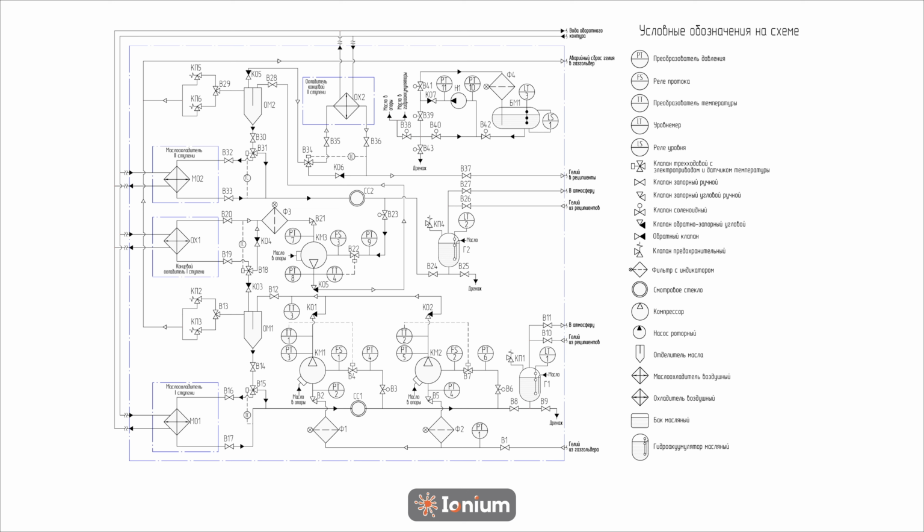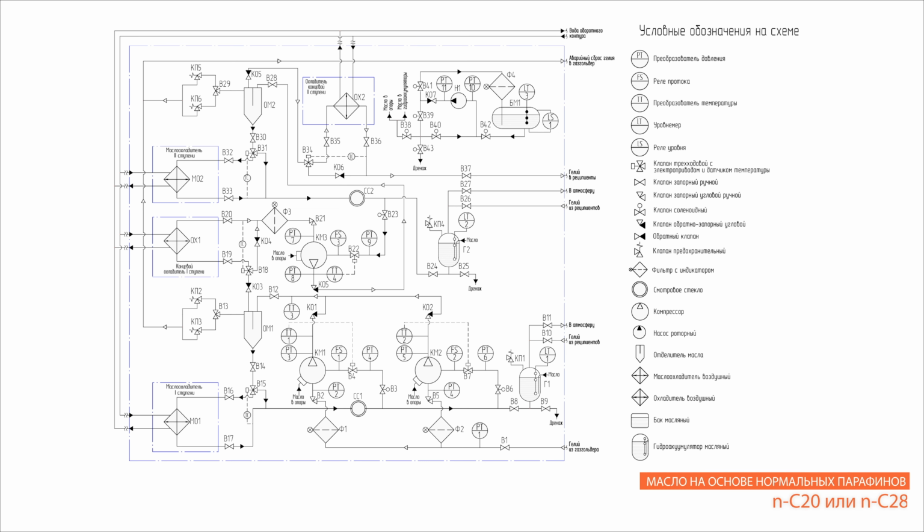To seal gaps between screws and casings, as well as to internally cool helium, an oil based on standard paraffins is used: n-C20 and n-C28, which include antioxidants and stabilizers like phenol. The machine is approved for use with a specified oil if the helium temperature at intake is above 0 degrees Celsius. The maximum operating temperature of the oil is 120 degrees Celsius.